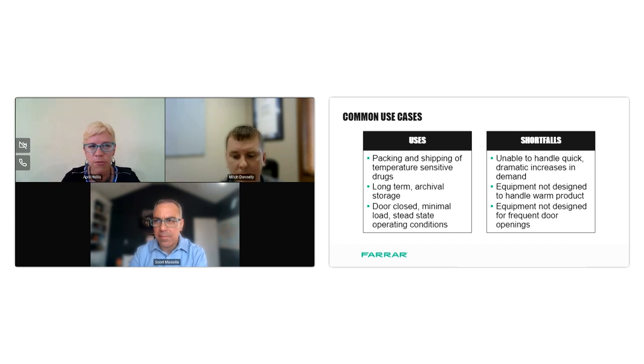Okay, and what would you say are the shortfalls of traditional or other technologies when used in those types of cases? So if we think about that, a lot of companies are now using the same equipment that's designed just to store material to also freeze it. And so when you start doing that, the systems don't have enough capacity in them to be able to do that. So a typical, if we pick on a ULT, typical ULT has 200 to 220 watts worth of capacity from the refrigeration system, while over 60% of that is used by the cabinet just to maintain the temperature that's inside of the unit. So when you think about that, you might have about 30 to 50, maybe 50 to 80 watts of cooling. When you put a lot of warm product in there, that's not a lot.